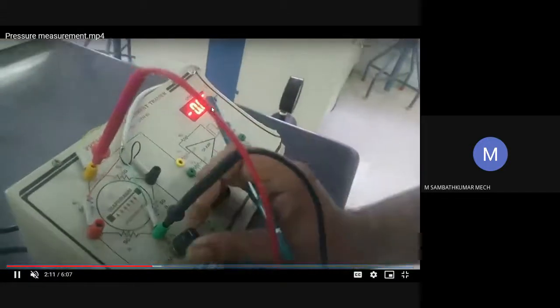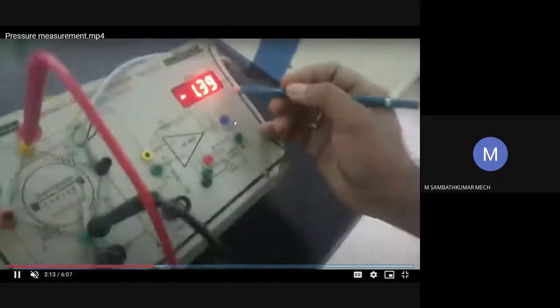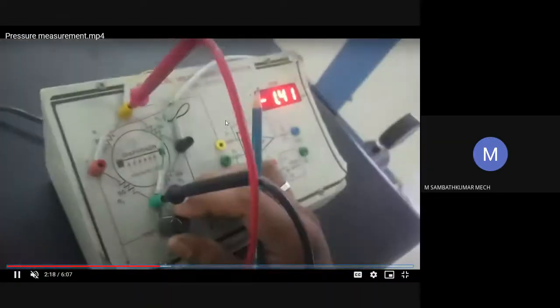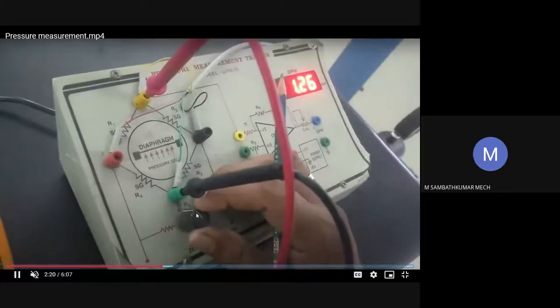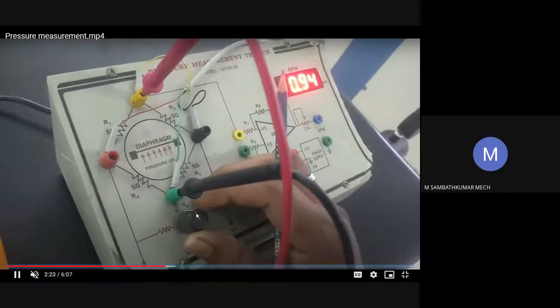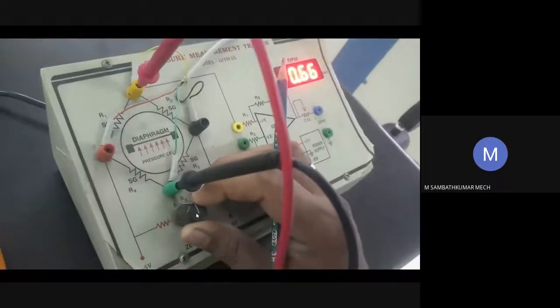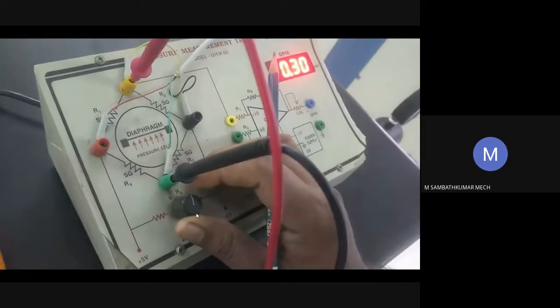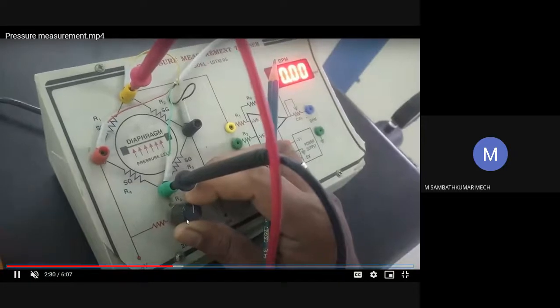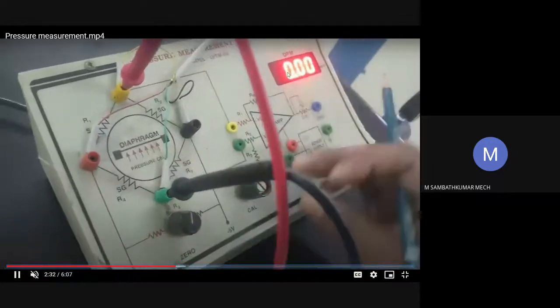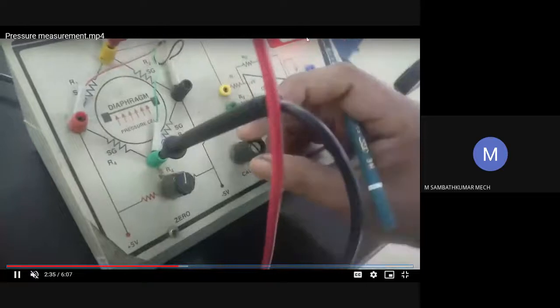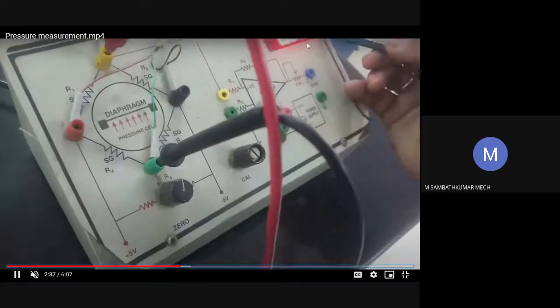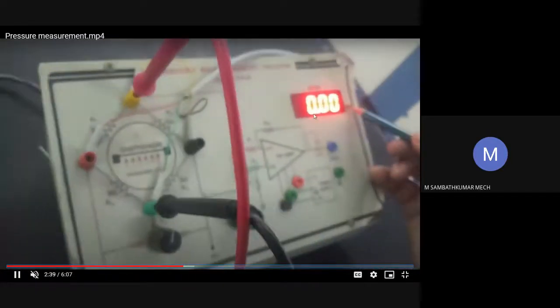So when you start, the value should be 0. Otherwise, if it is not 0, maybe some students have used it and the value may be varying. So you should set 0, and then only can you measure the correct value. Otherwise, the value will be changed. By using the 0 knob you can adjust the diaphragm pressure range, and if it is not 0, you can use the calibration knob to set it to 0.